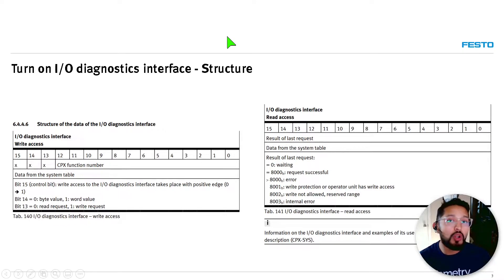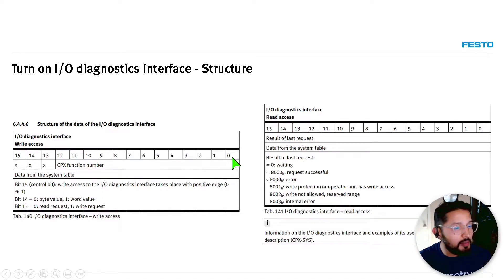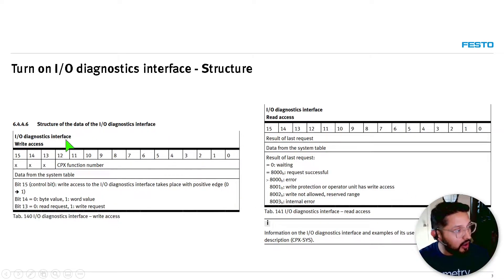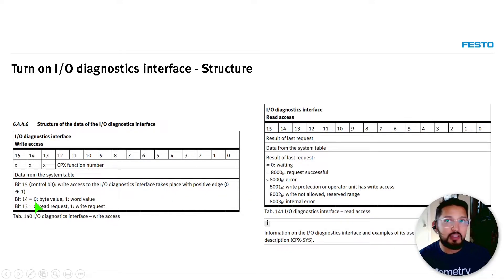Once you enable the IO diagnostics interface, there is a specific structure. You get two bytes — 16 bits — for reading and writing. On the write access: bits 0 to 12 are the CPX function number, bit 13 specifies if it's a read or write request, and bit 14 specifies the data type — we'll set bit 14 to 1 for a word value.